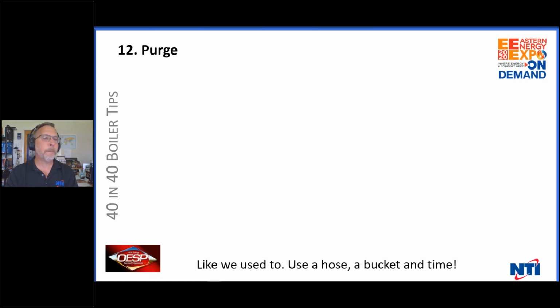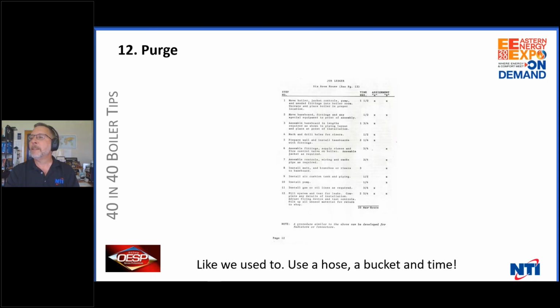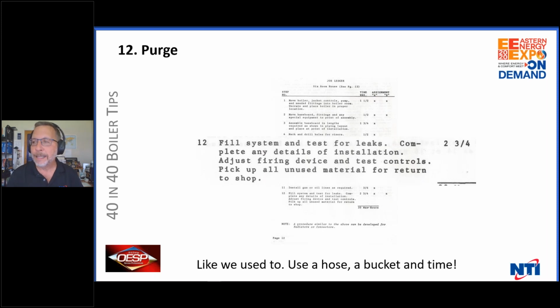Purge the system. Purge it well. This is a job ledger on the amount of time it takes to purge a system. It's amazing. Fill and test the system for leaks. Complete any details of the installation. Adjust the firing device and test all the controls. Pick up all the unused material and return to the shop.